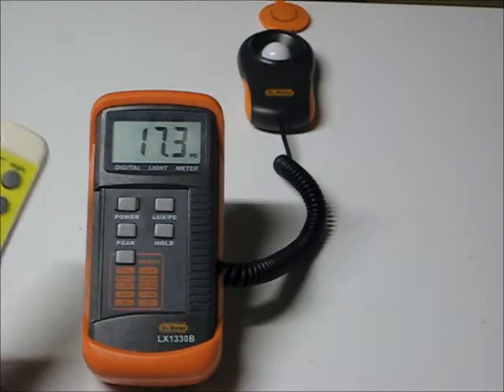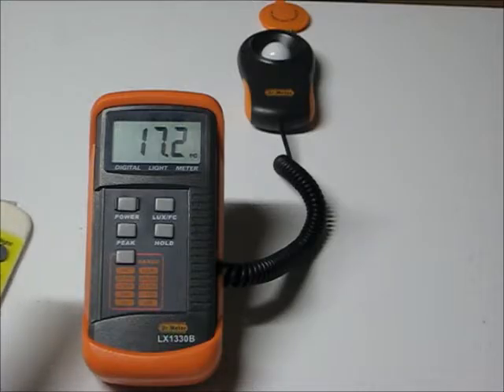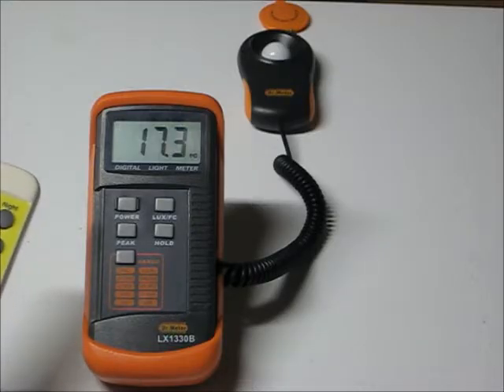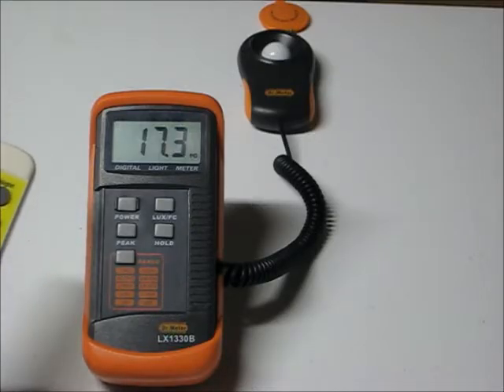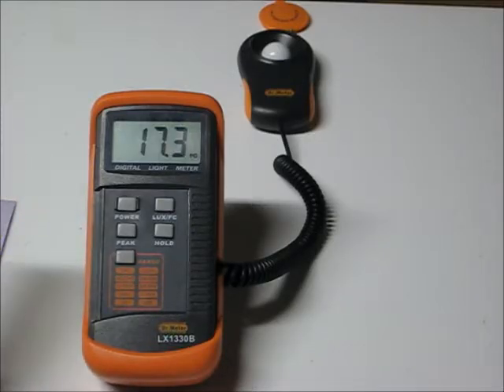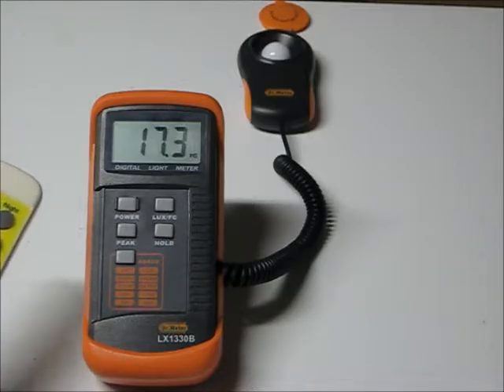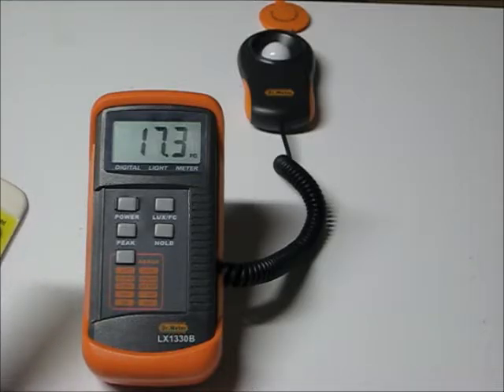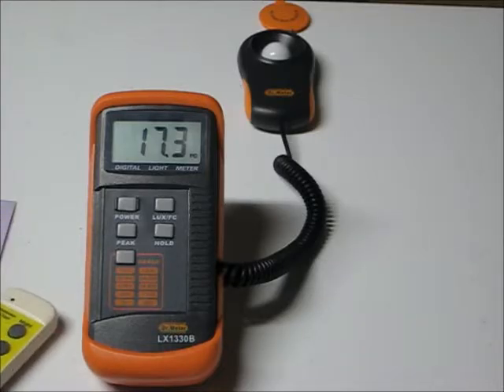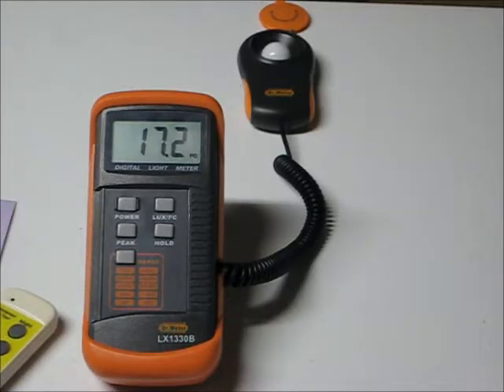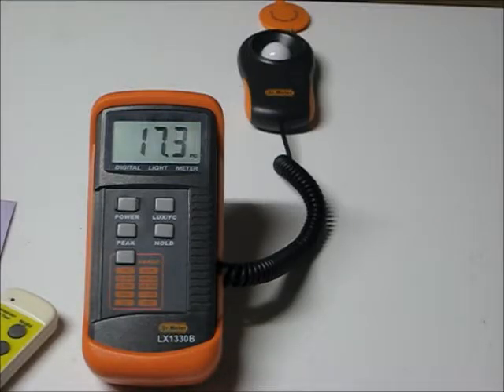Because it's a daylighting sensor, you have to set it up the way the manufacturer recommends. It takes a two point calibration. Otherwise, it's likely to reject it. And in the case of this one, it'll just wink at you. But this proves that you can set up automatic lumen maintenance for institutional tuning. That you can tune this thing down.